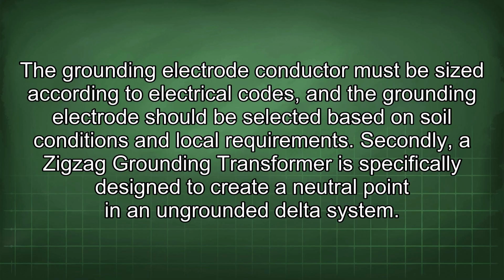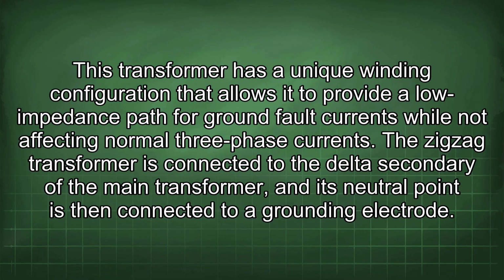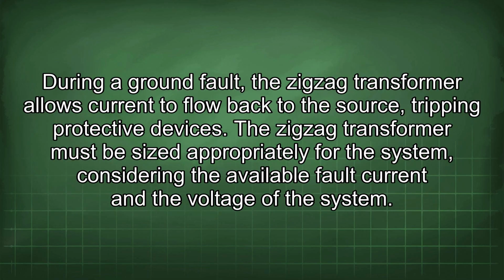Secondly, a zigzag grounding transformer is specifically designed to create a neutral point in an ungrounded delta system. This transformer has a unique winding configuration that allows it to provide a low impedance path for ground fault currents while not affecting normal three-phase currents. The zigzag transformer is connected to the delta secondary of the main transformer, and its neutral point is then connected to a grounding electrode. During a ground fault, the zigzag transformer allows current to flow back to the source, tripping protective devices. The zigzag transformer must be sized appropriately for the system, considering the available fault current and the voltage of the system.